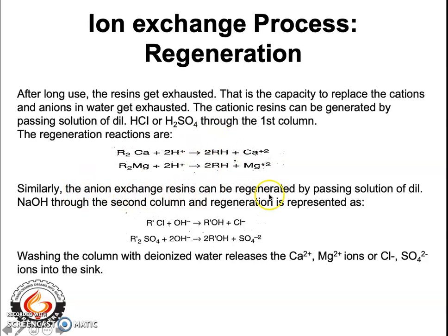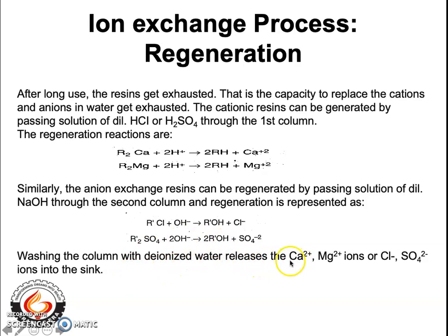Similarly, the anion exchange resins can be regenerated by passing a solution of dilute NaOH through the second column. The OH⁻ ions get trapped into the resin, and what comes out is chloride ions, sulfate ions, or any type of ions originally bound to the anion exchange resin. The resin beds — both the cationic and anion exchange resins — are then washed with deionized water, passing all the calcium ions, magnesium ions, or any other cations and anions out into the sink. This is the process of regeneration.